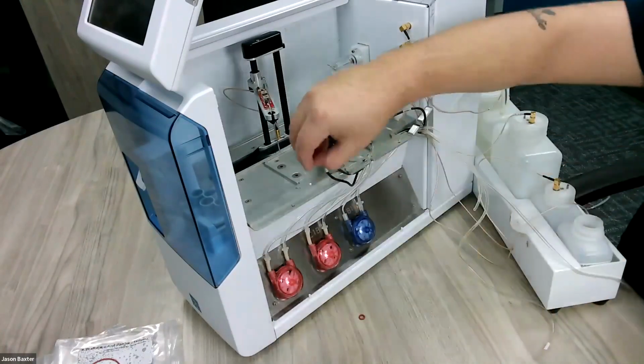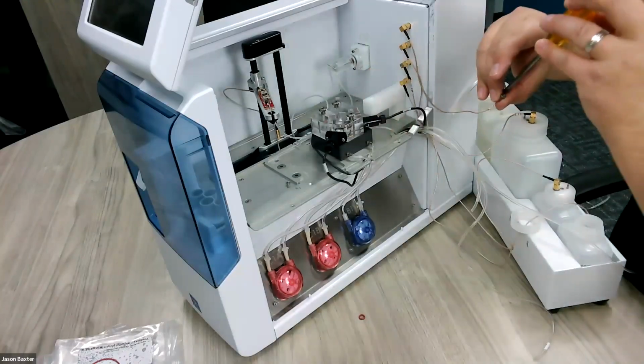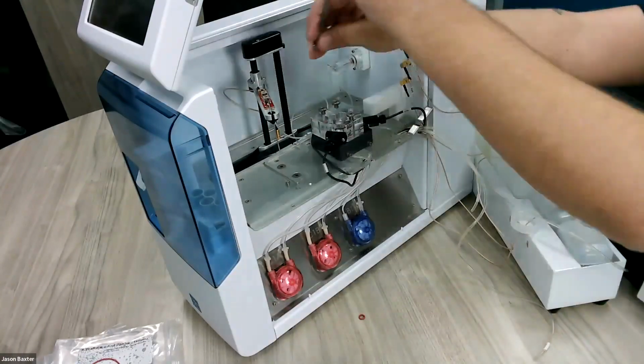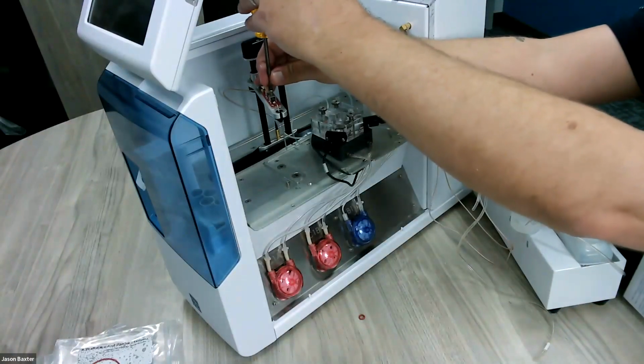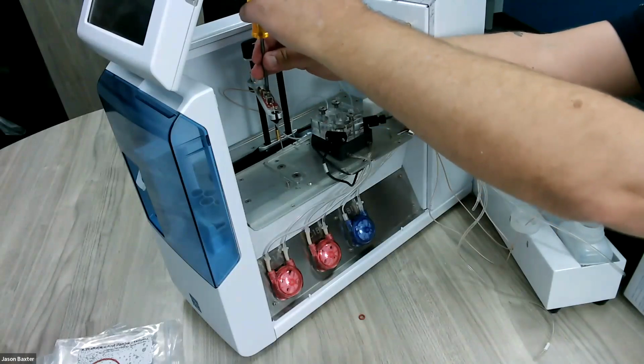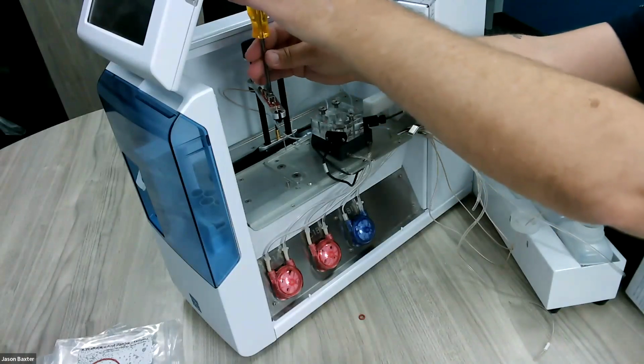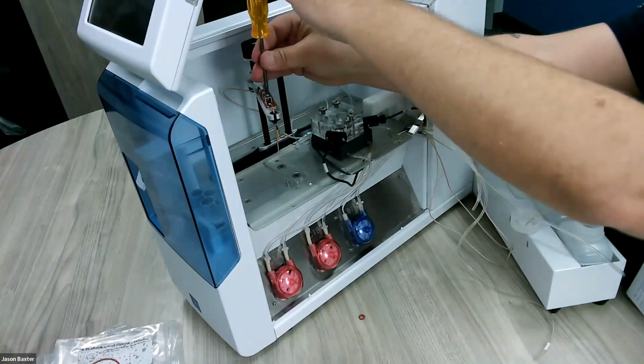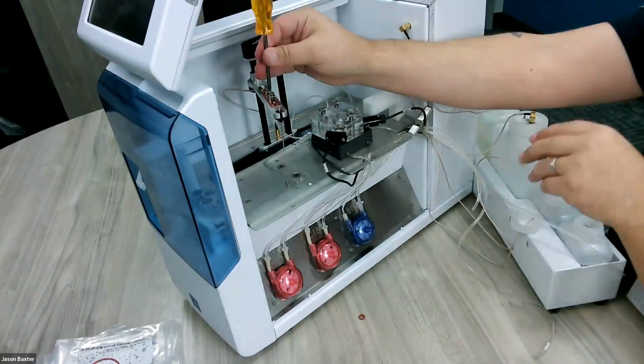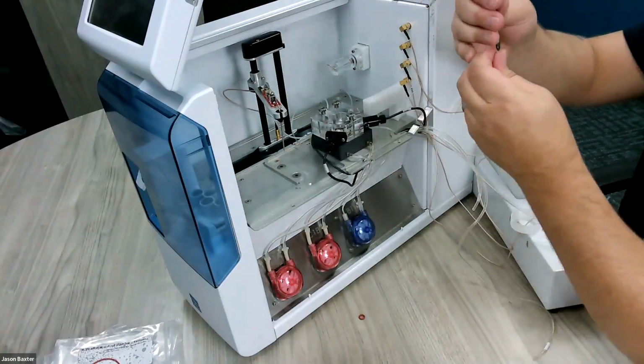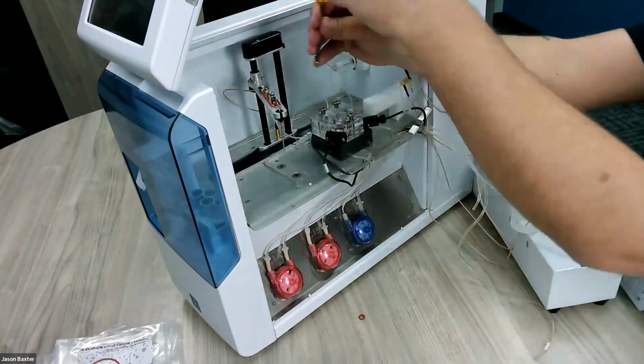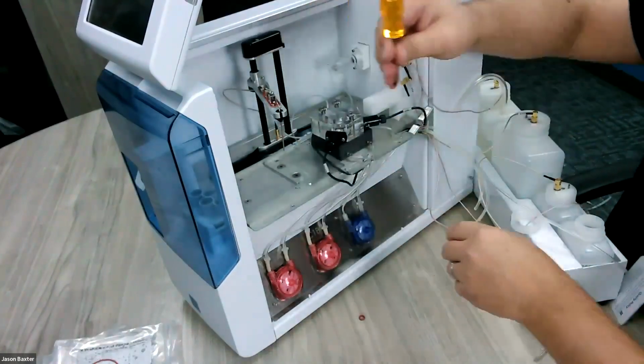Find your two mounting screws, or I'm sorry, your two retaining screws. Very critical point here, when you're tightening these up, these only need to be finger tight. If you tighten these more than finger tight, you will damage the sample needle, which will cause fluid detection problems when you try to turn the device back on and run.